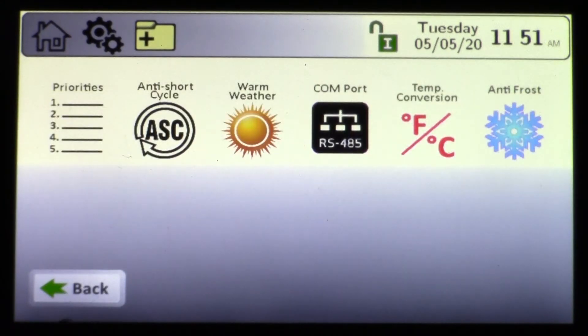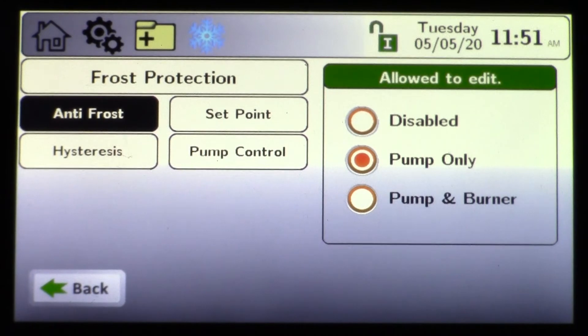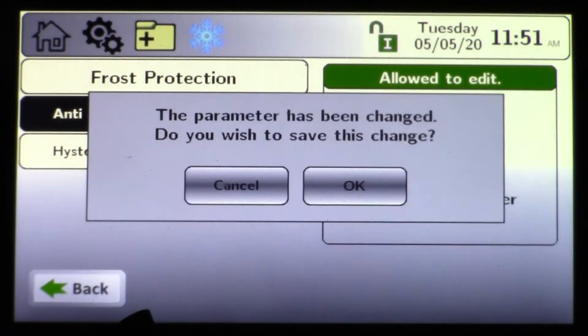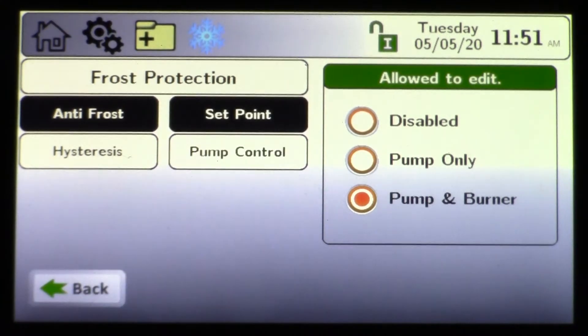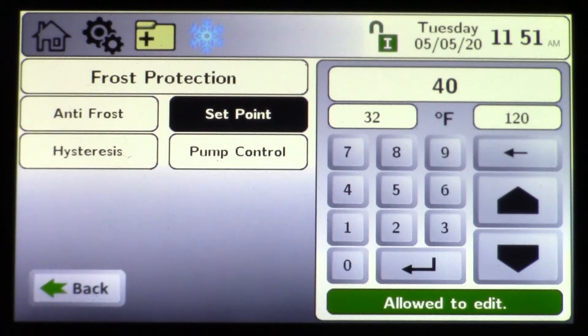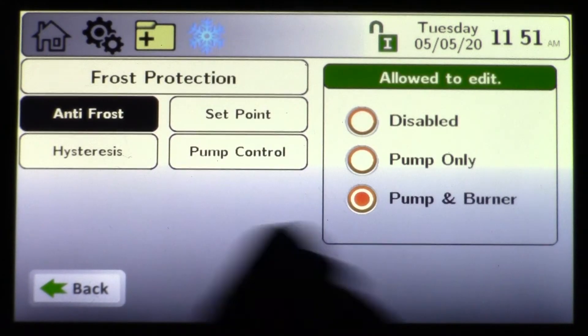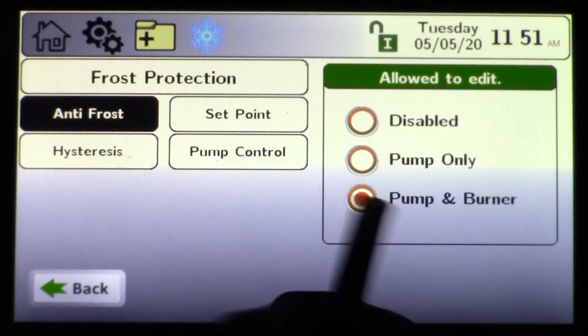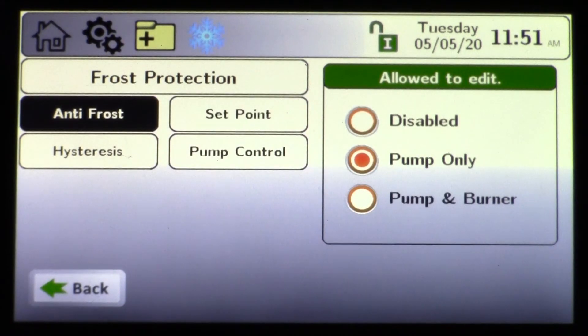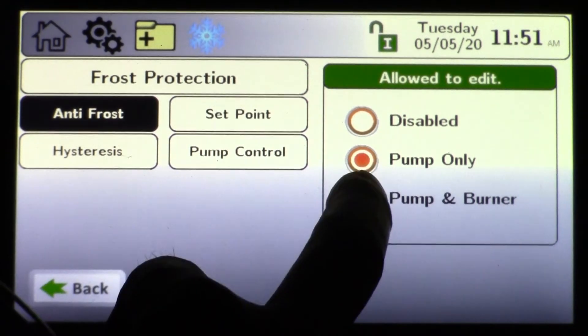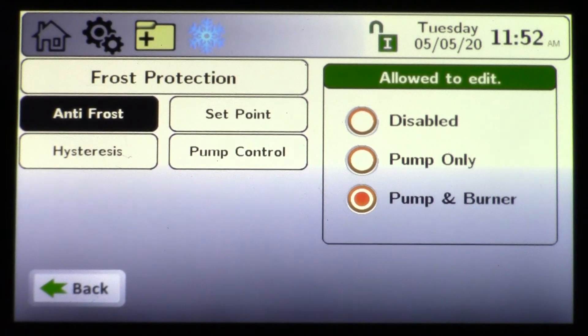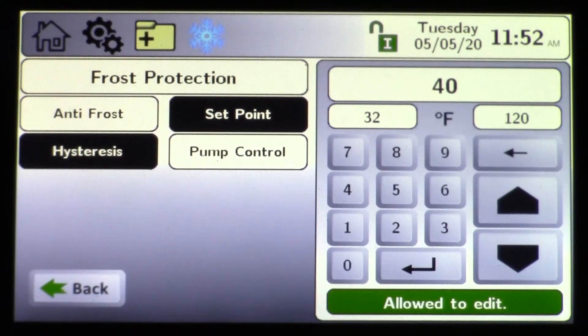Units — you can choose Celsius or Fahrenheit depending on your needs. Anti-frost protection is unique — it protects the heat exchanger. In this example, the set point defaults to 40 degrees. The boiler has an inlet sensor and an outlet sensor. If those reach 40 degrees, you can have pumps only — that allows the pumps to come on to move water through the heat exchanger so it won't freeze — or pumps and burner, which would attempt to fire and also turn the pumps on.